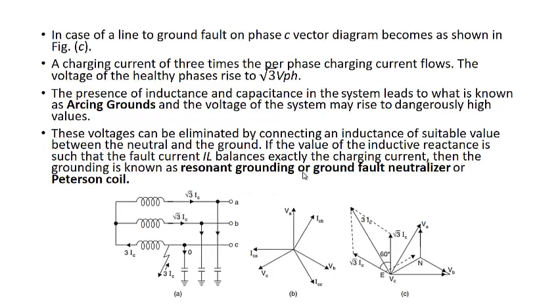But under abnormal conditions, let us say a line to ground fault occurs on phase C. That means phase C is at ground potential, or since this ground is not considered to be zero, the ground potential will now rise to the potential of C. That means we can see the neutral has shifted from this point to point C. Then the voltage of A, which was with respect to this neutral, that was this vector, will now be, because this neutral has shifted to point C, the voltage A with respect to ground, that means the ground is now at potential C, will be VAC. That is shown over here. This VA now becomes VAC.